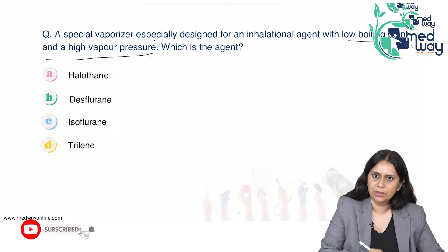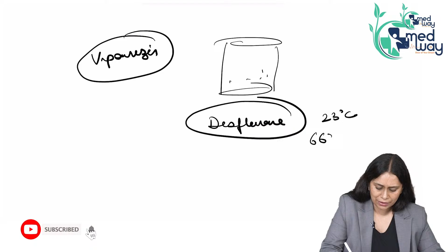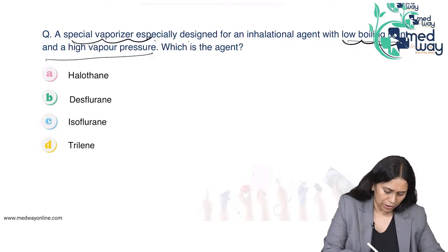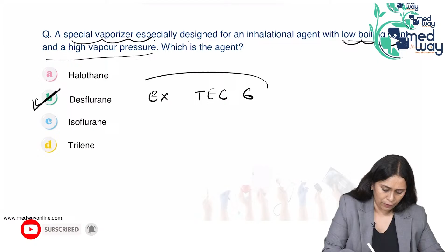Next question. A special vaporizer is specially designed for which inhalational agent with low boiling point and high vapor pressure? Now, as we discussed previously, a vaporizer is a device which is used for storing the inhalational and for delivery of inhalational. Most of the inhalationals have similar boiling points and vapor pressures. Only desflurane has a low boiling point. It boils at room temperature, 23 degrees Celsius, and it has a very high vapor pressure, 667. So, it needs a special vaporizing technique. So, desflurane requires a special vaporizer. One example of a special vaporizer is the Tec 6 vaporizer.